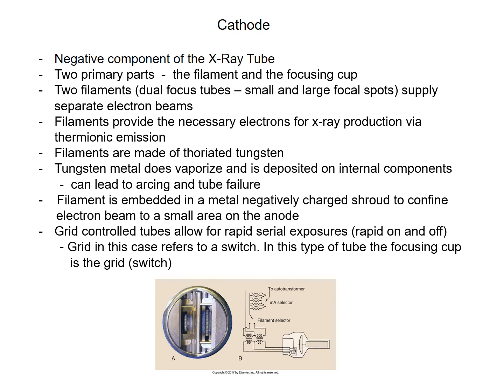Your book mentions grid control tubes. Grid control tubes are tubes that are used for rapid serial exposures, which means very quickly on and off, like in digital angiography, for example. Now, the grid, though, is not the type of grid that we talk about, grid with lead strips in it, radiolucent strips, and radiopaque strips that confine the scatter radiation. This type of grid in electronics is a switch, basically. It allows for the electricity to quickly go on and off. And in this type of a tube, what we call a grid-controlled tube, the focusing cup actually is the grid. It acts as the switch. You want to keep that in mind. Sometimes you see that question in review books. What acts as the switch in a grid-controlled tube? And it would be the focusing cup.